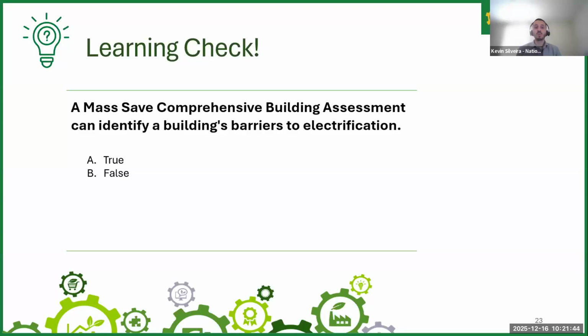So the answer is true. In a CBA, we will look and identify different barriers to the electrification, be it the existing distribution system needs to be replaced, or that the existing electrical infrastructure to the building is undersized, or that the grid capacity is not there. There could be constraints on the grid.